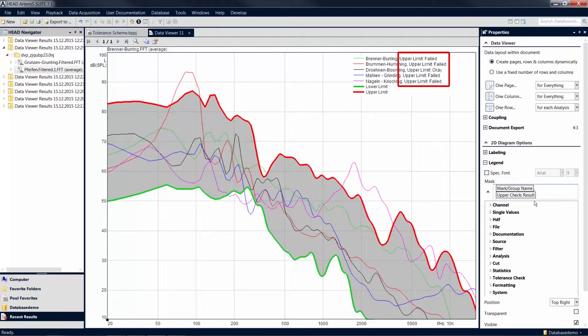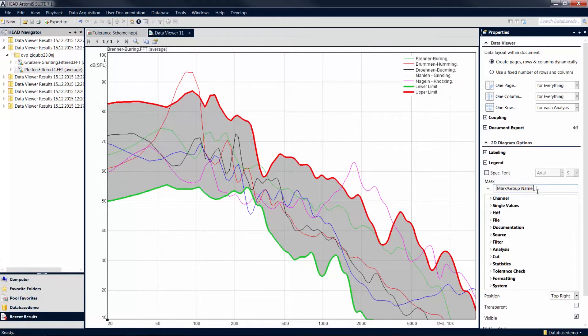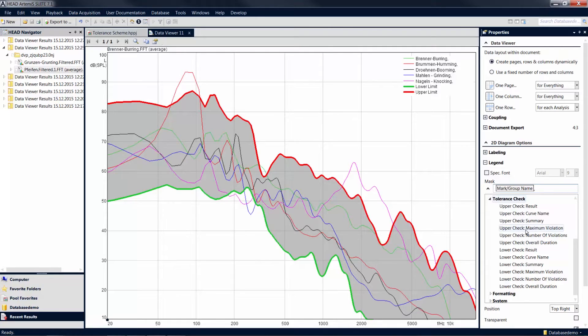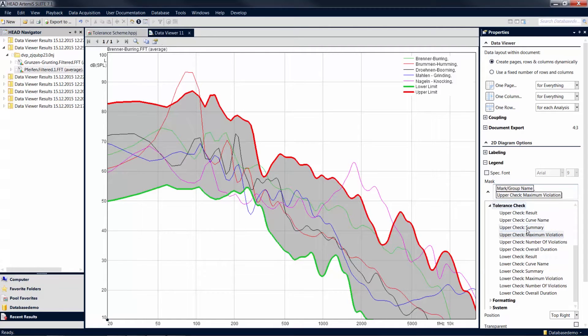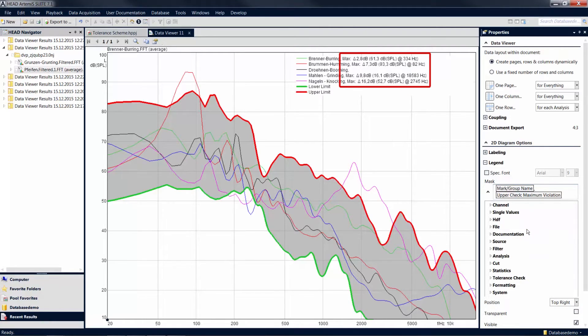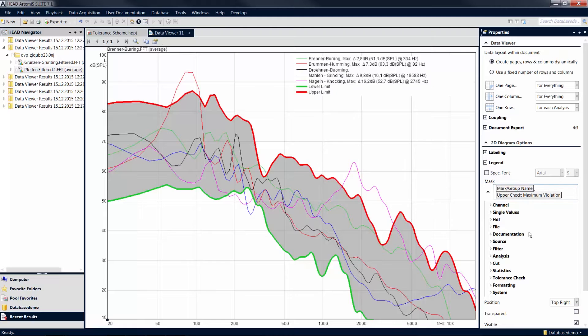Enable the option Upper Check Result to get information whether or not the tolerance was violated. If you want numeric information on the individual tolerance violations to be displayed, select the option Upper Check Maximum Violation, for example. Now the largest violation, along with its position, will be displayed for each curve. This allows you to determine quickly and precisely which measurements exceed the specified limits.